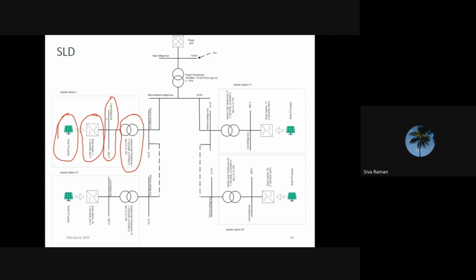Generally, the low voltage side, that is the inverter terminal voltage, is from 500 volt to 690 volt. In the inverters which came between the years 2013 to 2018, mostly the voltages are around 500 volt. Nowadays, most of the inverters are coming with 690 volt. So that is the general terminal voltage of the inverter. The typical inverter duty transformer LV voltage is the solar inverter terminal voltage, for example 690 volt. And the high voltage side will be at 11 kV or 22 kV or 33 kV, 11 to 33 kV.